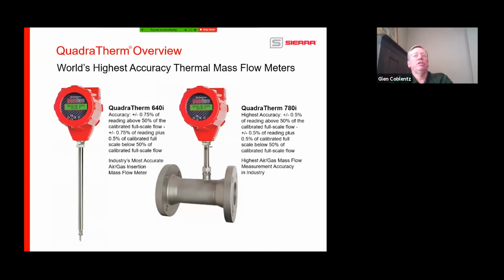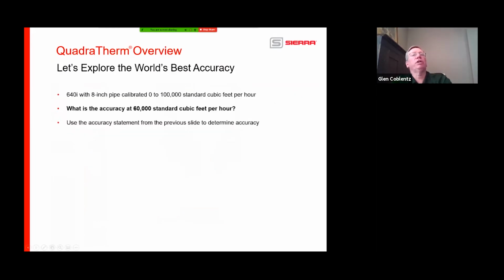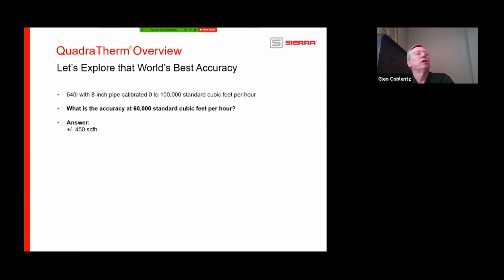Now, with this statement here, let's figure out some accuracy. So if we have a 640i with an 8-inch pipe calibrated at 0 to 100,000 standard cubic feet per hour, what is the accuracy at 60,000 standard cubic feet per hour? Use the accuracy statement, previous slide, to determine the accuracy. So everybody go ahead and try to figure that out. We're going to be looking at the chat box to see who the winner is. I want the right number in there, and I want the right unit of measure. So we're starting to see answers show up, and there we have a winner. Nicely done. It's plus or minus 450 standard cubic feet per hour.